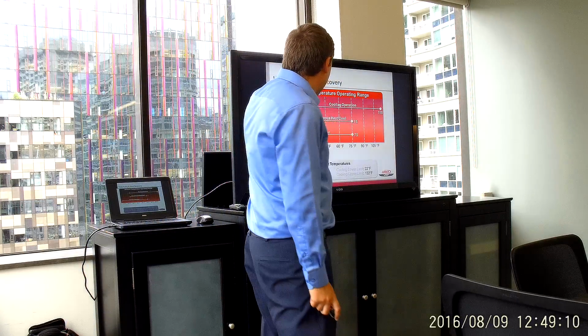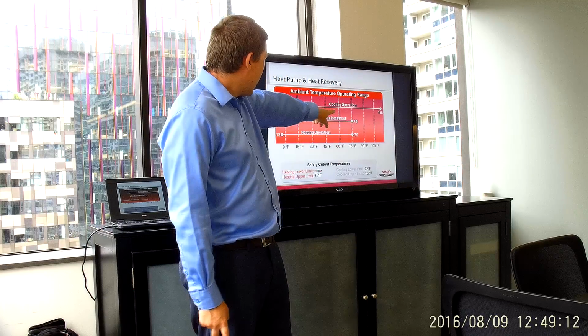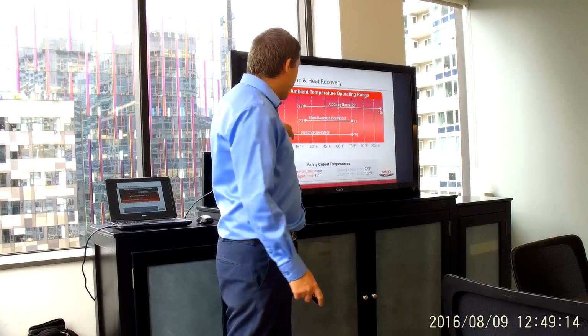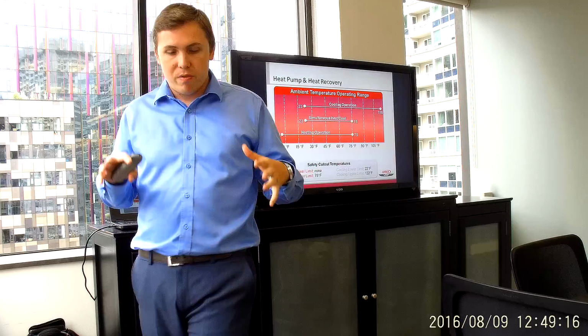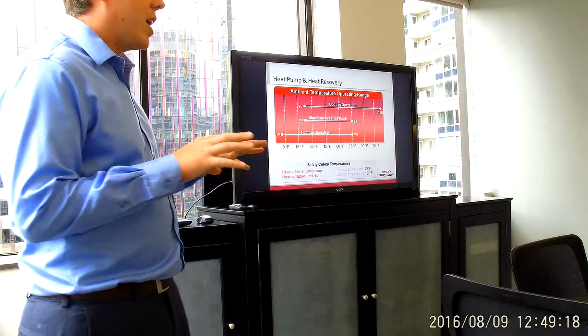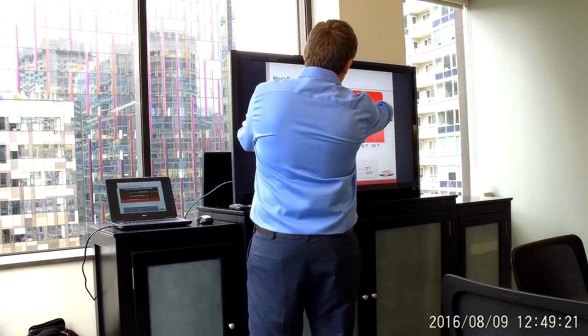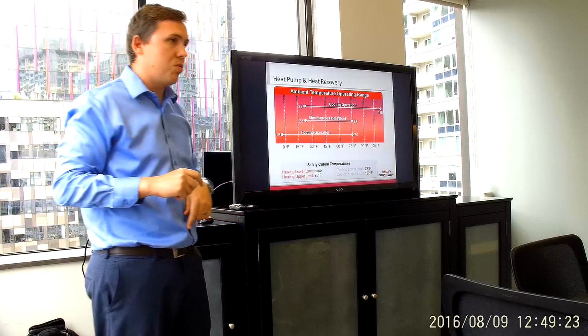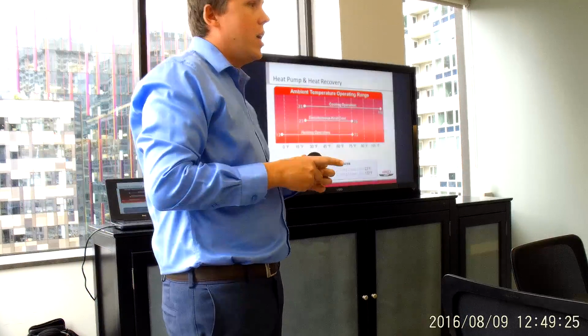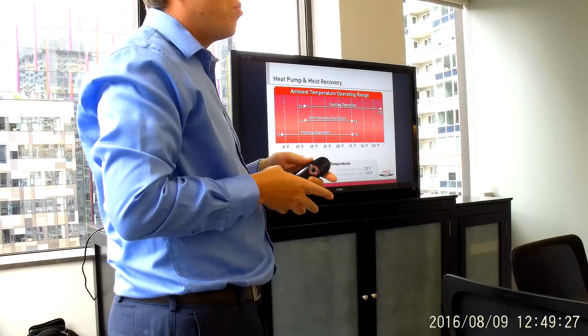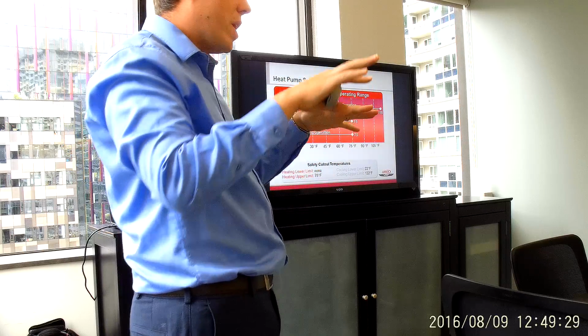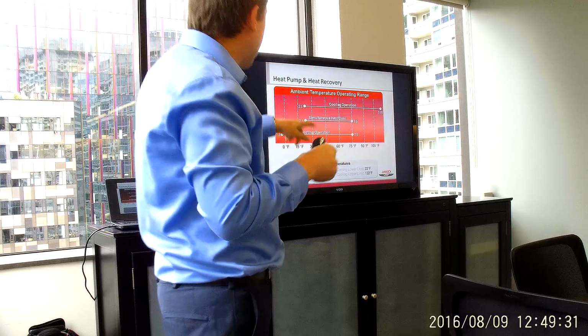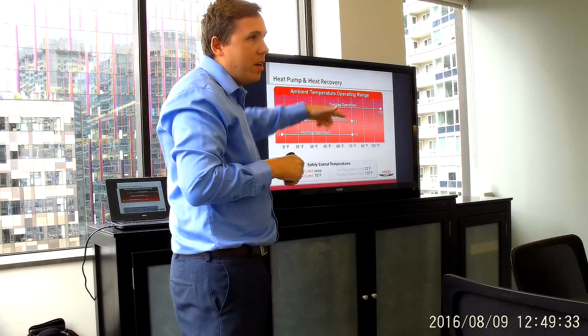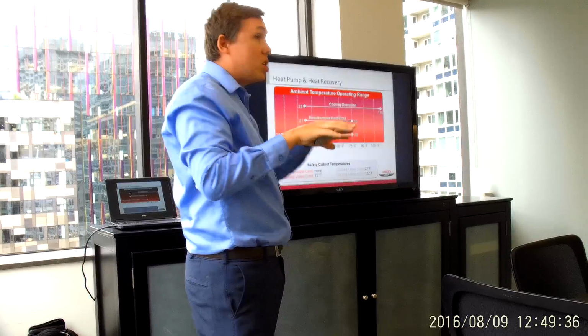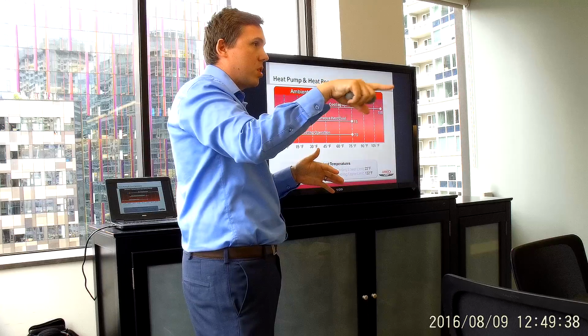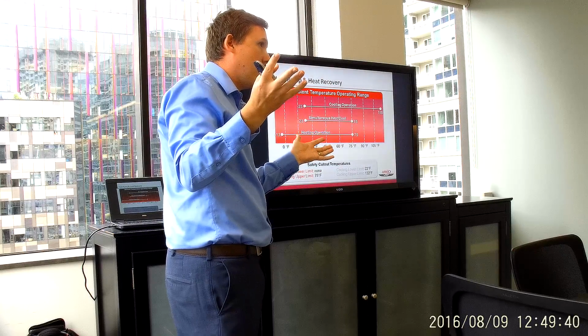You'll notice the simultaneous heating and cooling here. The reason why that's at 23 and not at minus 13 is the fact that it tries to balance itself out. I can't tell you it's simultaneous heating and cooling, it's going to do the full range. I don't believe any manufacturer can do that. Because very simply, that shoulder season range, when it goes into that cooling and then back into that heating, the cooling limit is still set at 23. And the heating limit might be set at minus 13, so it'll go down there and then the heat recovery will take place internally. It's not going to not do heat recovery.